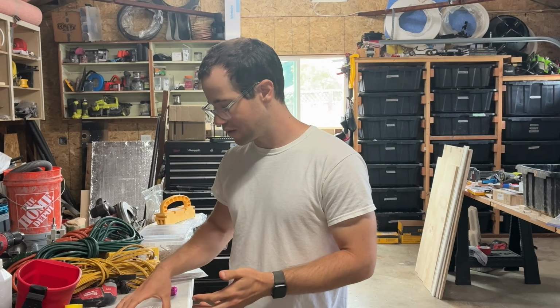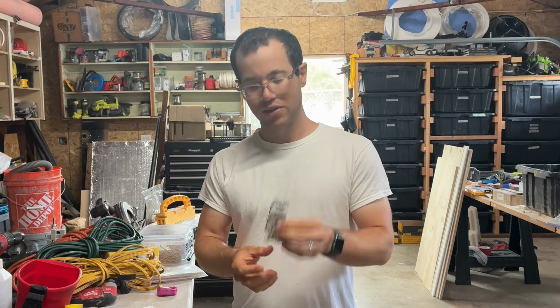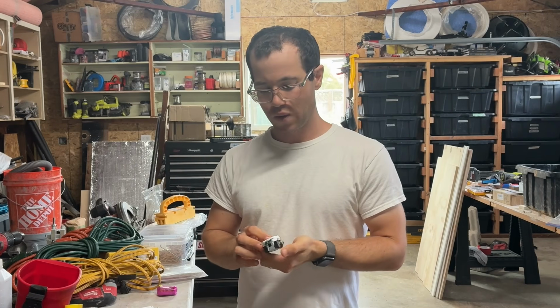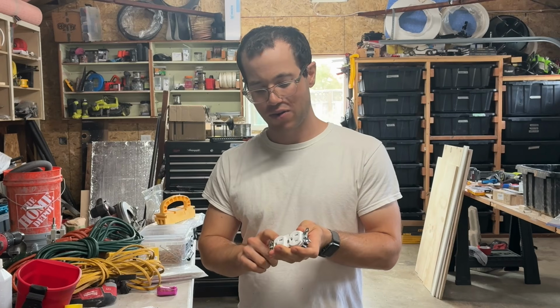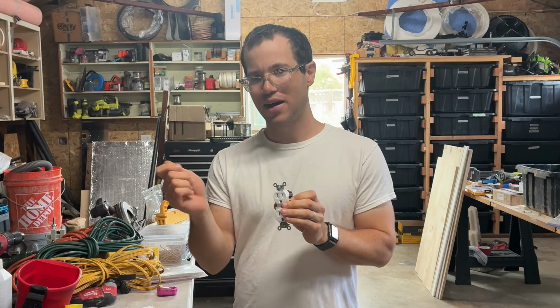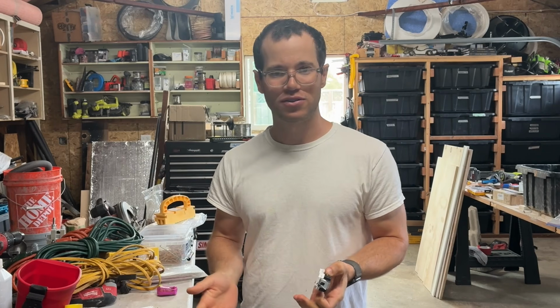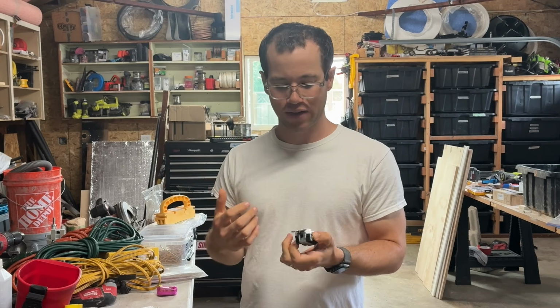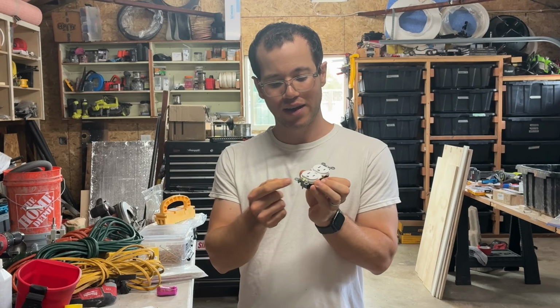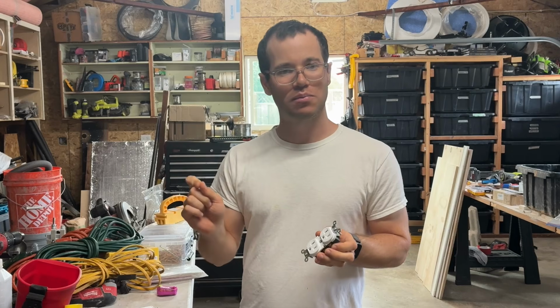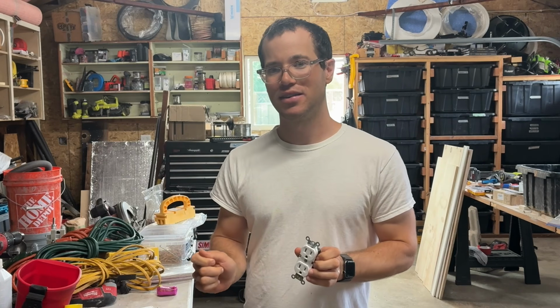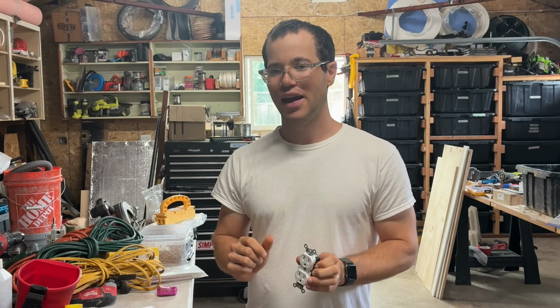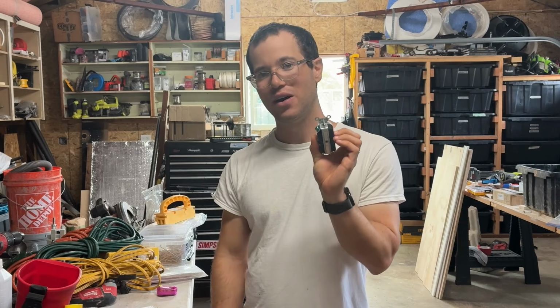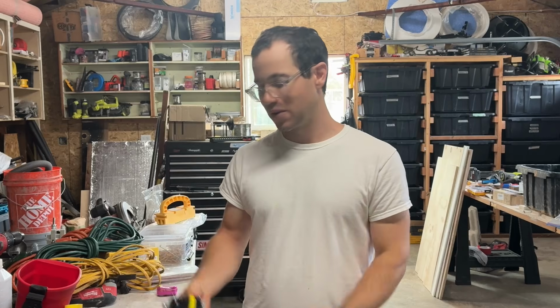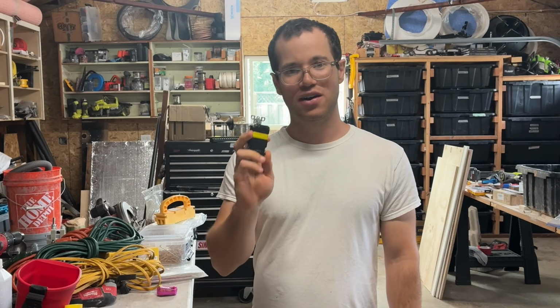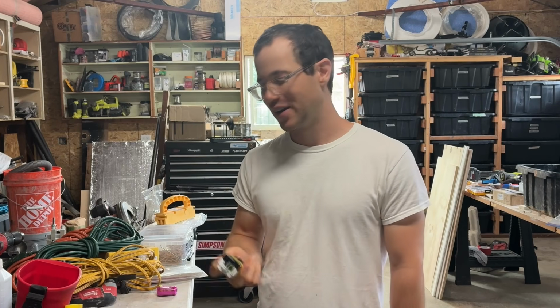With proper ground wires, modern circuits have these green screws right there. When you properly wire a house and there's ever a short - say that black wire touches the metal enclosure of your toaster or hair dryer - the hot wire has an immediate path to ground and the circuit breaker will trip. So you've never energized that equipment enough for a human to get electrocuted, and you've protected the equipment too. A proper ground wire protects you and the equipment, but if all you want is to protect yourself, that's where these GFCI outlets are a safety requirement from the National Electric Code, and you do need to install them.